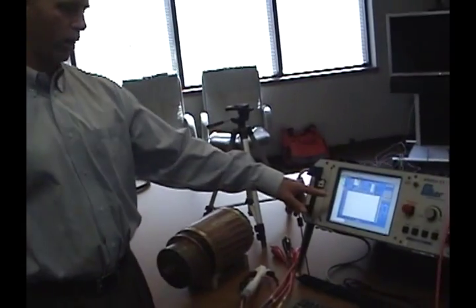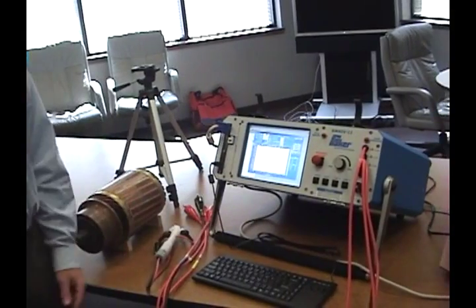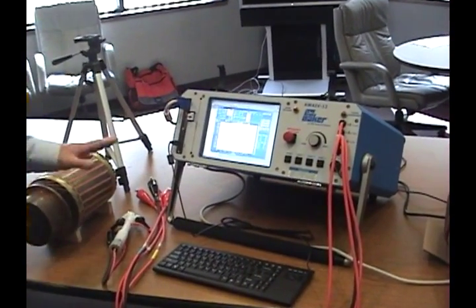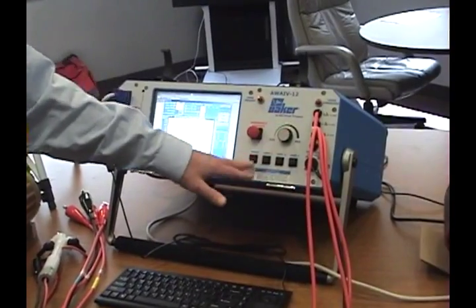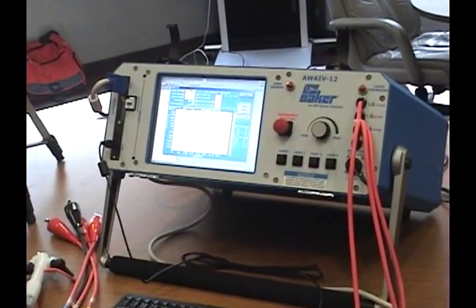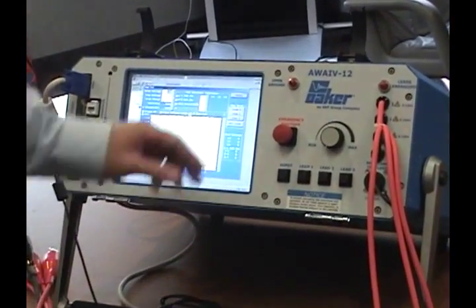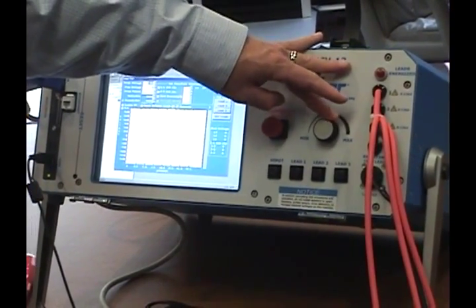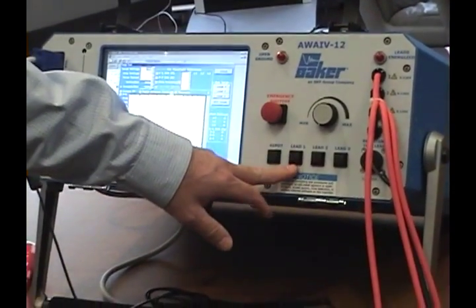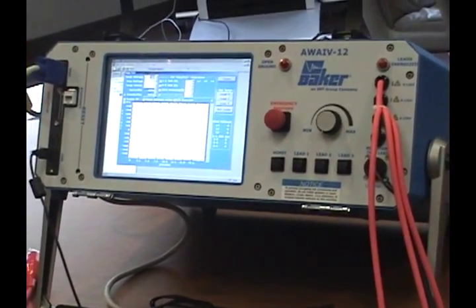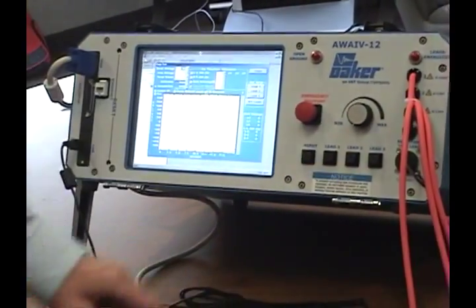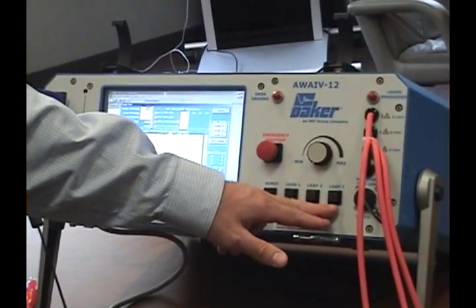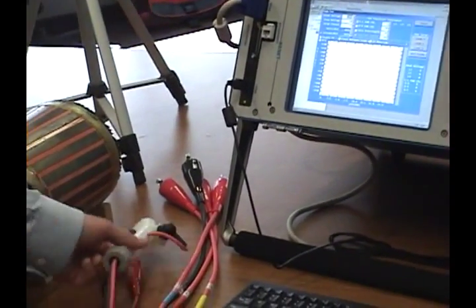With the software set to the parameters that we want, we will utilize the manual functions on the AWA to perform the surge test. We have the voltage ramp rate here. We have lead one to surge down lead one. Of course lead two would surge down lead two and lead three would surge down lead three.